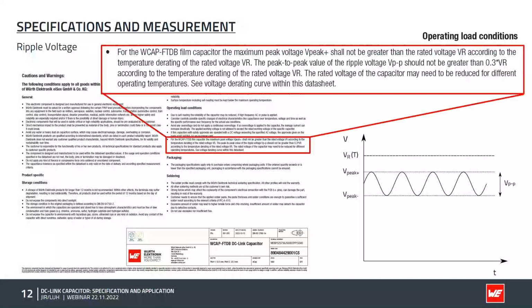In this case, I want to show you this point in the section called operation load conditions. Here we are trying to say that there is a limit to the voltage ripple at the capacitor, and it should never be greater than 0.3 times the rated voltage. The repetitive peak voltage value should never be larger than the rated voltage. This is another rule that may be overlooked.